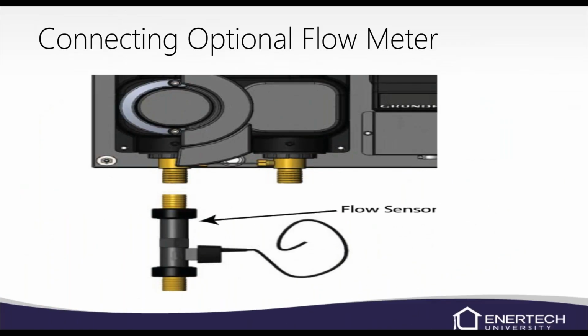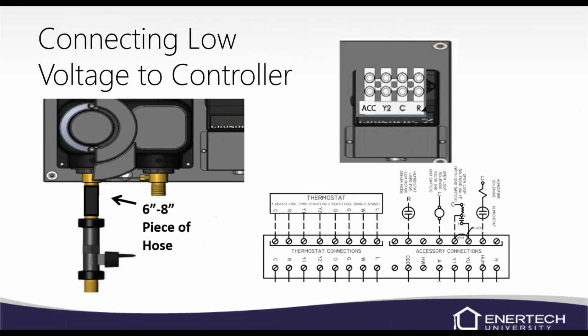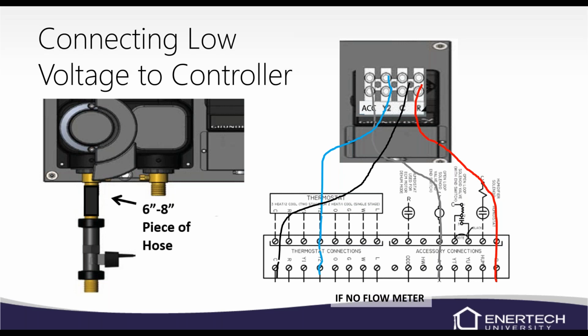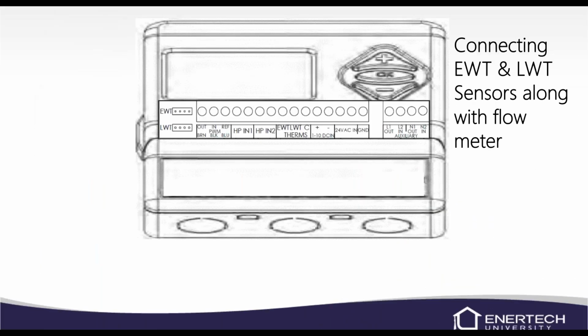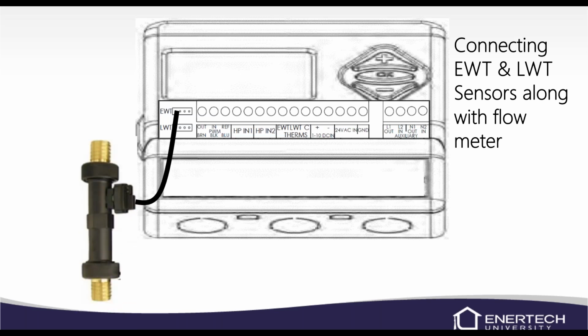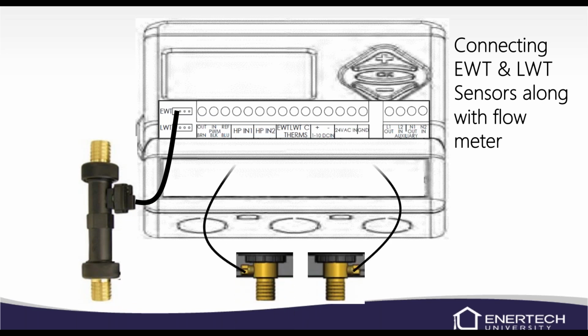Connecting the flow center, this is a flow sensor. Make sure you put a little rubber hose piece in between the flow center and the flow sensor connector. The wiring is pretty simple: common to common, your Y2 to your Y2, ACC to A, and R to R. And that's when you're using a flow meter. If you're not going to use the flow meter and you're just going to base it on temperature, then you would wire it a little bit differently because you have sensors, and the sensors for the flow meter would just plug right into it.